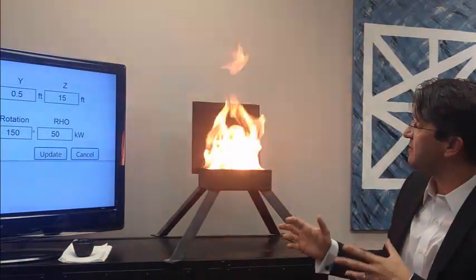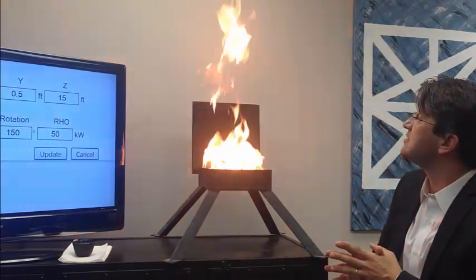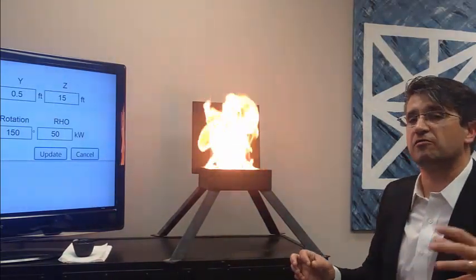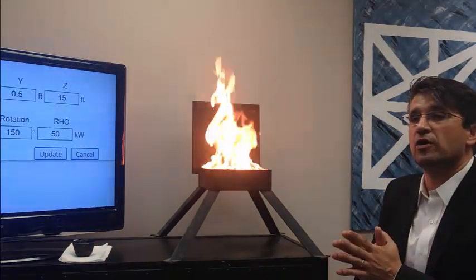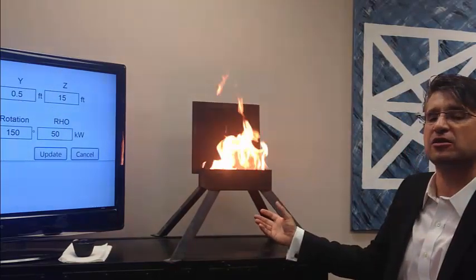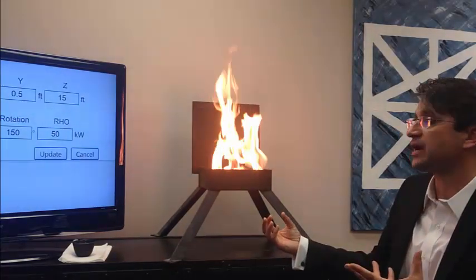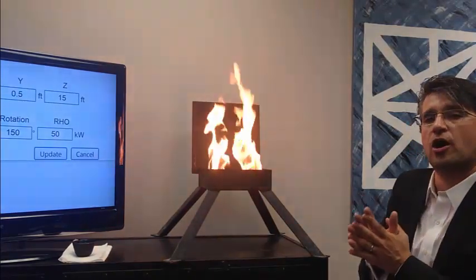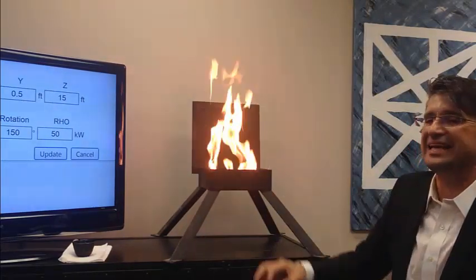So with that, this is a very good representation of the different fire sizes that we're intending to detect. And what you're looking at right here, this is typical of a medium fire. And this is also typical of what equipment vendors will provide you data on. So you'll see that this is significantly larger than the 10 kilowatt fire that would be representative of a zone A or a higher risk area. So the information for how big of a fire are we looking for is going to be something that's going to be designated in that radiant heat output.